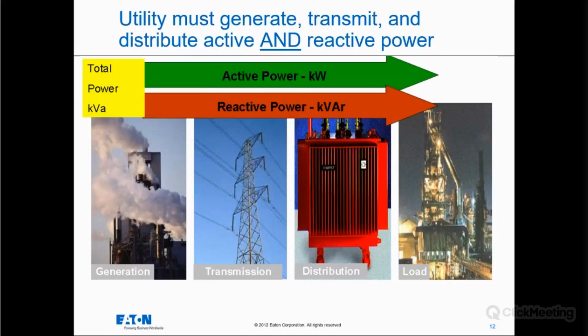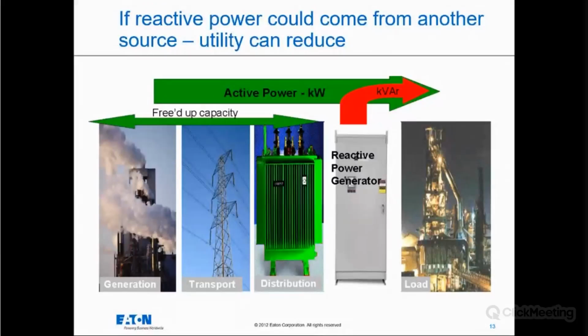The most efficient and better way to do it is to supply that reactive load locally instead of pulling it through the electrical system. So you could supply the reactive power that the motors and things in your facility desire instead of pulling it through the electrical system. And it also makes it a more efficient, cooler running system as well. So those transformers will have that load removed from them, making them operate in a much more efficient, cooler fashion. So if you've ever looked at transformer curves, you know that for every degree that you can remove off a transformer, it extends the life of that transformer dramatically.